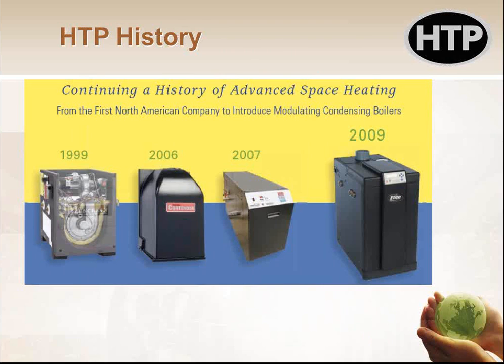And they were really one of the first guys to have condensing boilers in the North American marketplace. Everything else prior to that was made in Europe and sometimes imported over. But the United States finally got on the bandwagon, 12, 15 years ago, whatever it was. So that first one there where it says 1999, that's actually what we call the Munchkin boiler. Some of you guys may have seen those in the field. Some of you guys love them. Some of you guys hate them. The reasons you hate them are probably because they're the first ones that were here and misinstalled very frequently. Like people didn't do the primary-secondary piping and then wondered why the boiler didn't run very well. So things like that. But once everybody got educated up to speed, those boilers became very reliable.